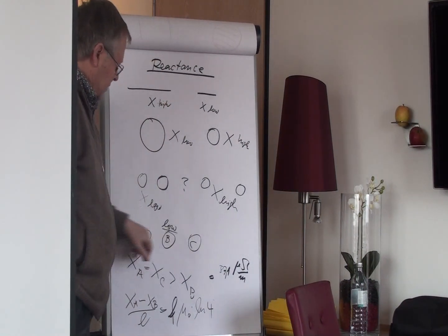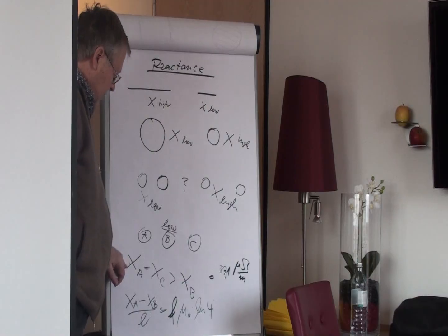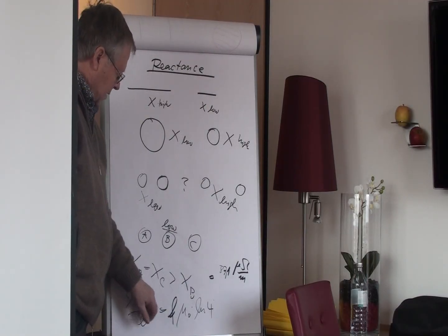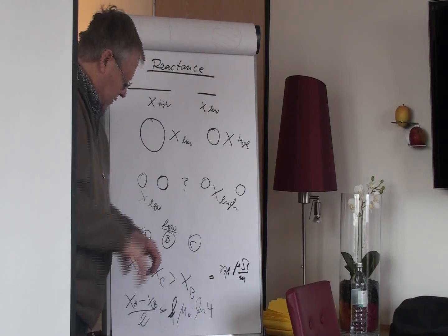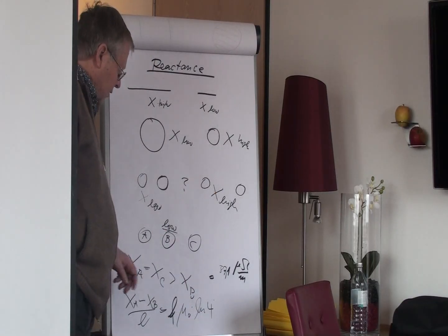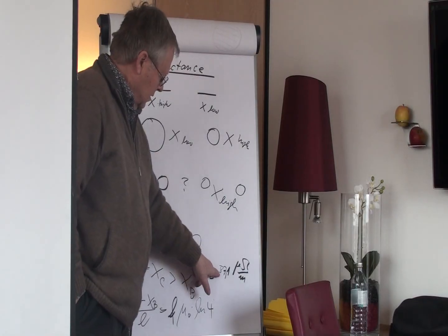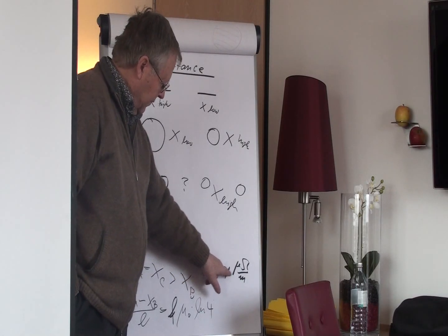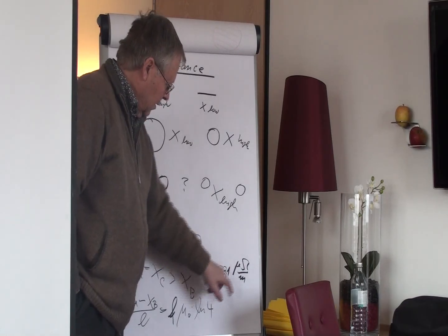If you have this system, there's a difference between the outside and the middle phase, and this is given by this formula, if this is a long distance. And you can calculate this as 87 micro-ohm per meter.